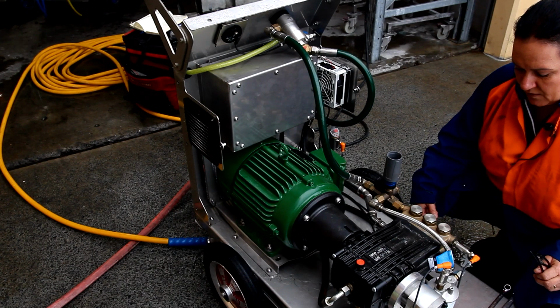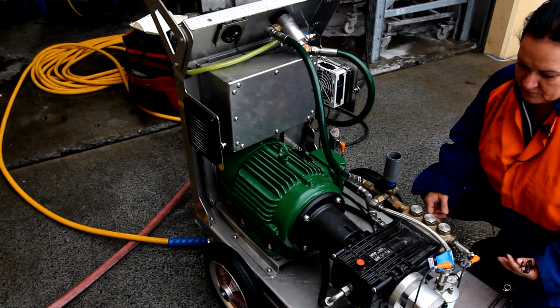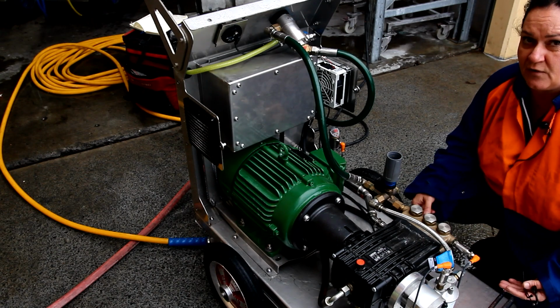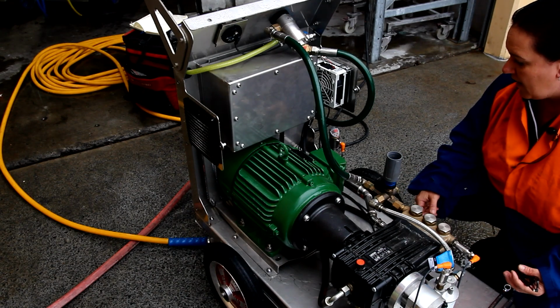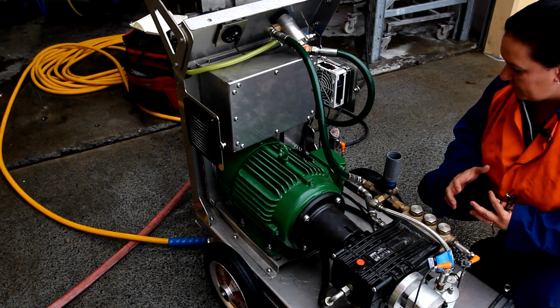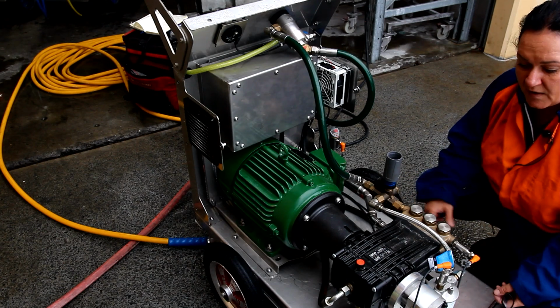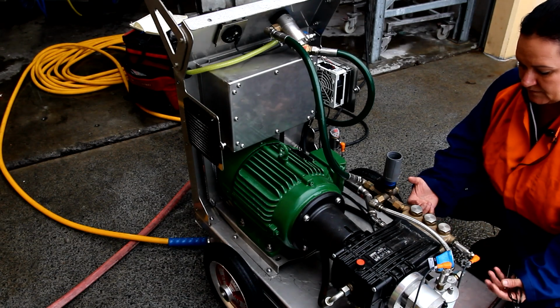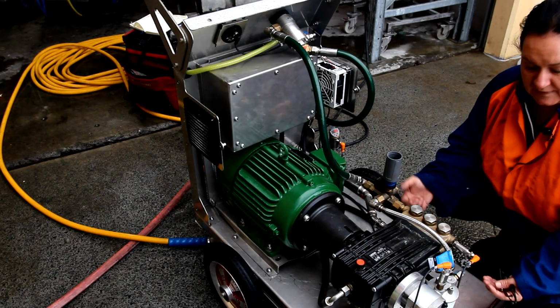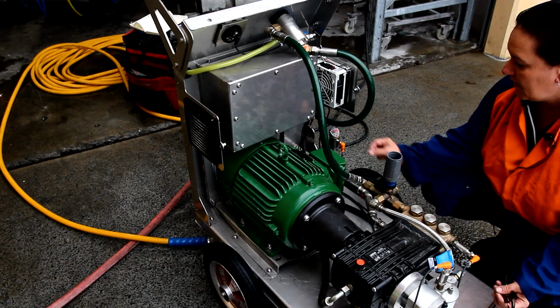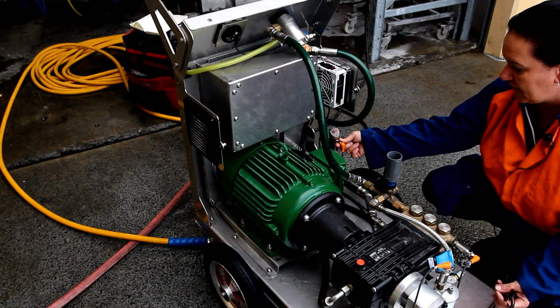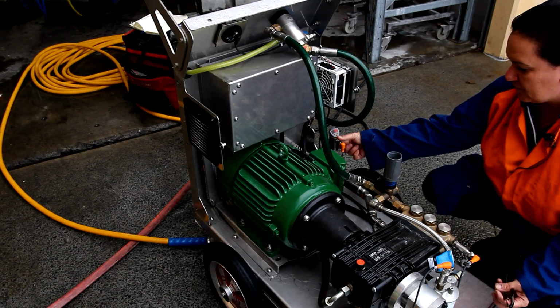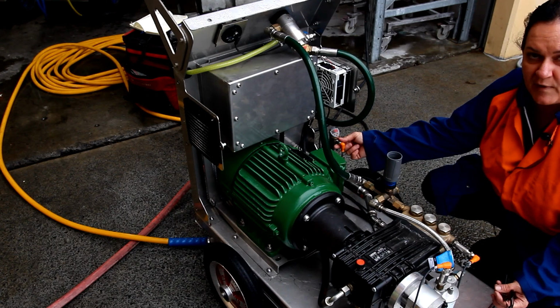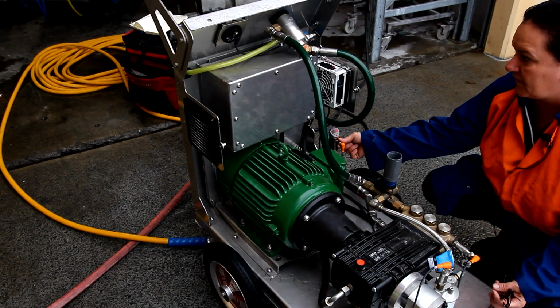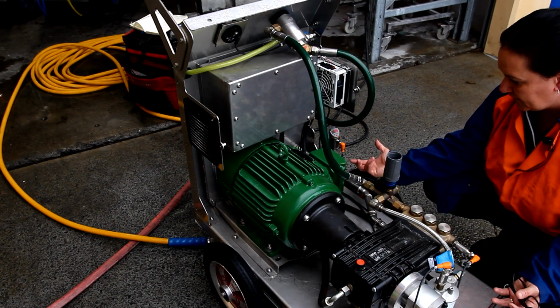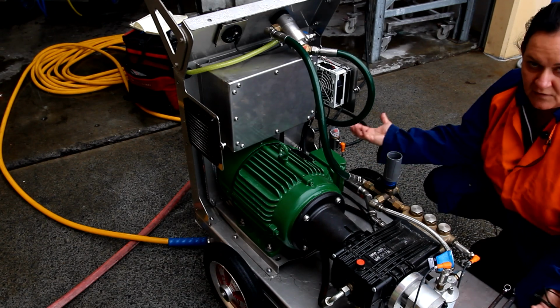So when the cover is removed, whether that's weekly or definitely not longer than monthly, the first thing we want to know is there's no visible leaks or weeps anywhere. And the other main thing is we want to check all our electrical connections. Basically these all have an M12 fitting. Just through normal sort of vibration, we want to know that nothing has gotten loose. Obviously if the lead is loose, then that no longer works.